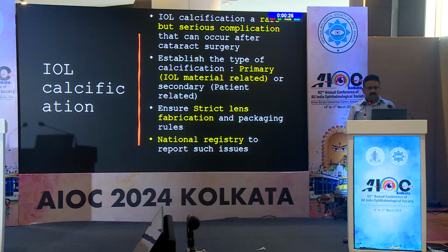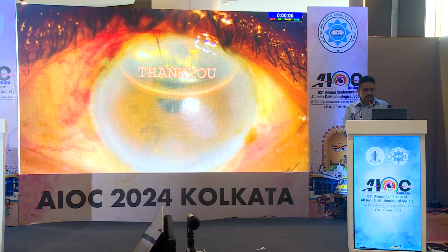A word about IOL calcification: when approaching such a case, we should make out whether it's primary, which is IOL related, or secondary, which could be patient related. And as an organization, we should ensure strict lens fabrication and packaging, and a national registry, maybe at AIOS level, to report such issues. Thank you.